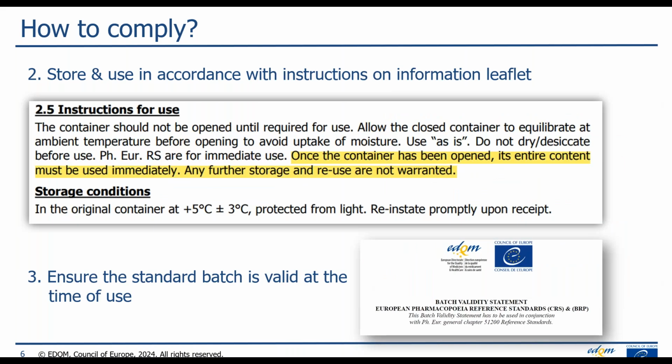Okay, the next thing we would check then is whether the reference standards are being stored and used in accordance with the instructions on the information leaflet. This here is an example of the leaflet for ibuprofen, I believe. I've just highlighted here that once the container has been opened, its entire content must be used immediately. And this is a common issue we see on inspections, whereby the primary reference standard is essentially being used as a multiple use standard, which is not in fact in line with the instructions for use.